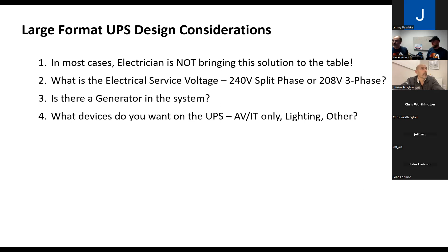If it's a generator, we already know the answer to runtime. But sometimes generators aren't around, or there's something else, so if we have some kind of runtime requirement, that's good to know. We also want a list of all the loads going on here, since battery time is dependent on the electrical load, the lower the load, the longer the battery lasts.